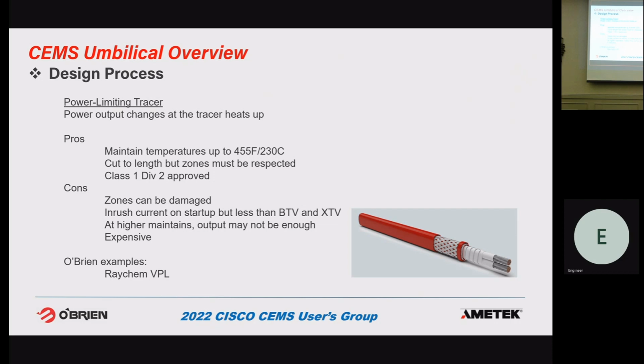So the next style is called power limiting. So power limiting has self-regulating qualities, but it's a zone style tracer. Everybody know what a zone style tracer is? So it's different than a self-reg. So it has self-reg qualities, but zone style tracers, they look similar, but internally they are made up of individual parallel circuits. These parallel circuits are set up in things called zones. So you have zone lengths between 13 inches and about 49 inches. And every zone essentially operates as its own circuit, but it's a parallel circuit. And you have the next one and the next one.